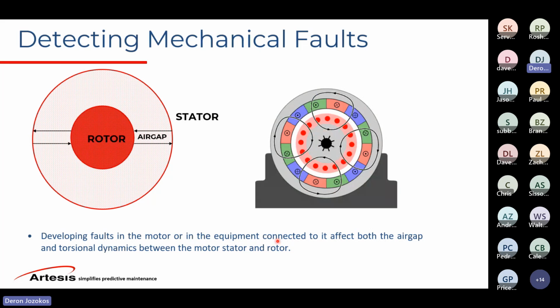Now, a common question we get is, okay, you're monitoring the voltage and the current, so naturally you can get the electrical side of things, but you're installing this unit into the MCC bucket, but my cooling tower is 150 feet away, 50 feet in the air, all the way out there. How can you see a bad bearing on my fan, through the MCC bucket, which is all the way over here? And the answer is, we're using the motor as a sensor. So in the beginning, we said we don't use any sensors. We don't put any sensors out on the machinery. You already have your sensors out there. They're the motors. And actually, more specifically, the air gap between the rotor and the stator.